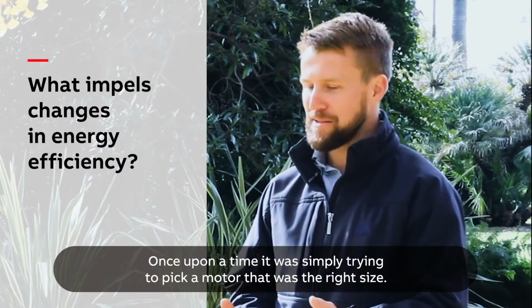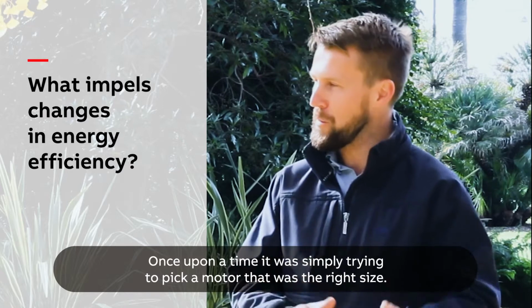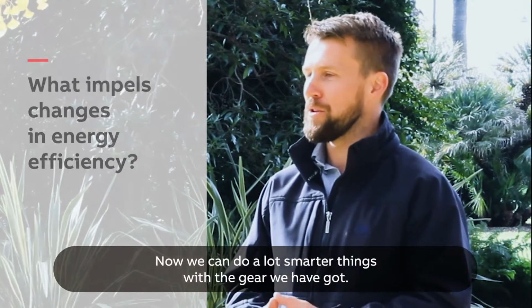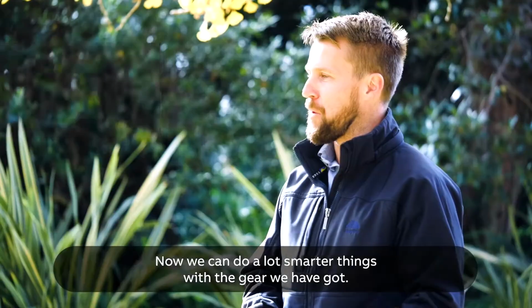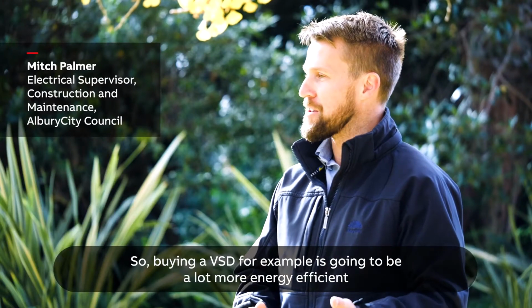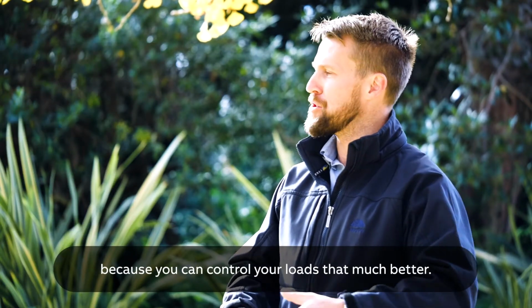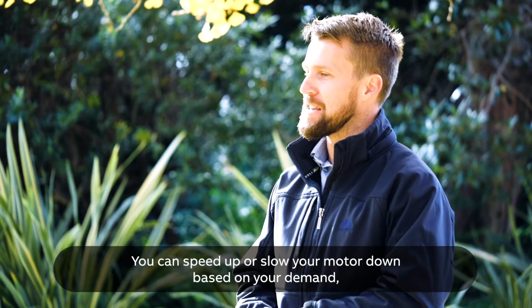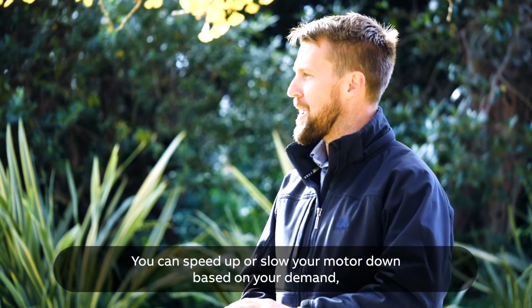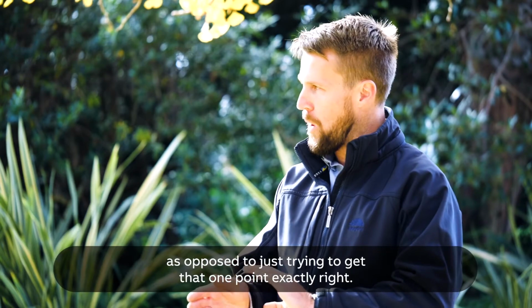It was just simply trying to pick a motor that was the right size, not too big, not too small. Now we can do a lot smarter things with the gear that we've got. So buying a VSD, for example, is going to be a lot more energy efficient because you can control your load so much better. You can speed up or slow your motor down based on your demand, as opposed to just trying to get that one point exactly right.